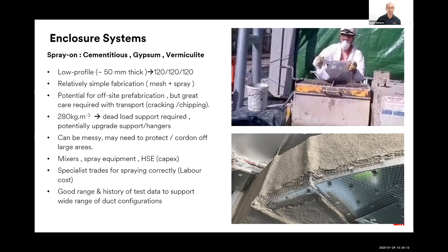Relatively simple fabrication, it just involves installing some mesh and spraying, or potentially troweling a liquid material on there, sometimes in multiple coats. There is some potential for off-site prefabrication, but great care needs to be taken with transportation, because it's a rigid material and there's potential for cracking or chipping. It can be quite heavy. The material itself is typically 280 kilograms per cubic metre, so some consideration of the supports for the duct would be needed, whether they need to be upgraded.